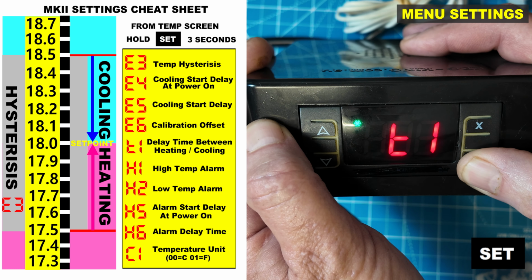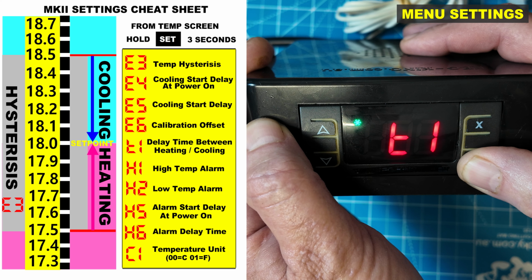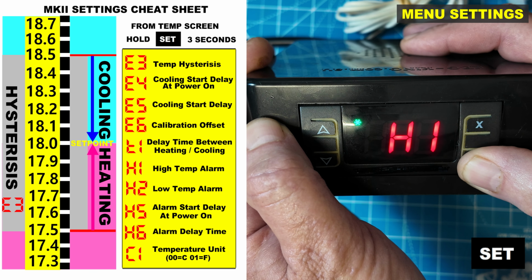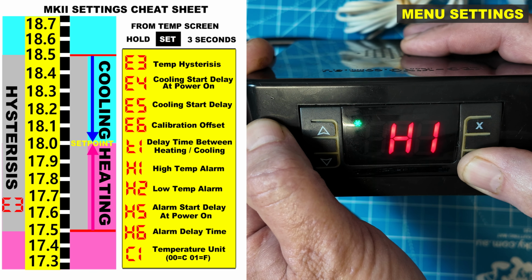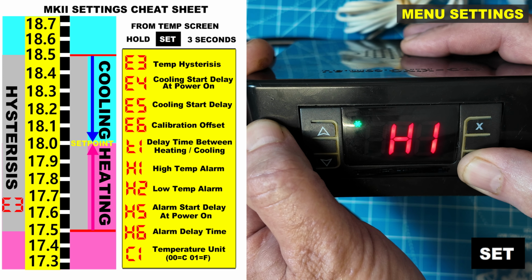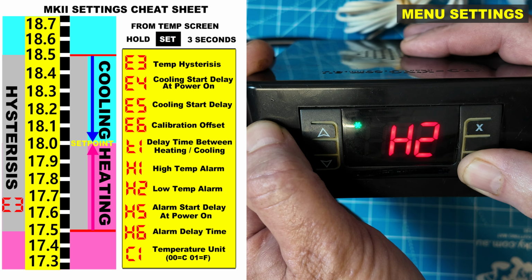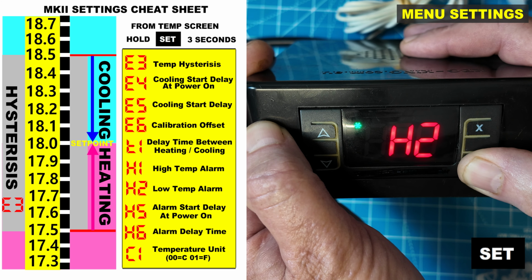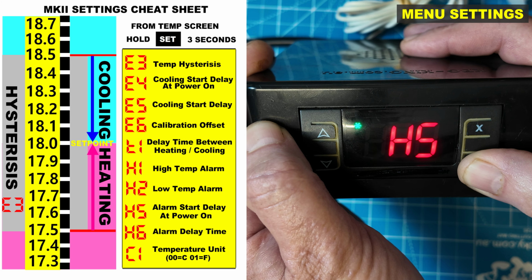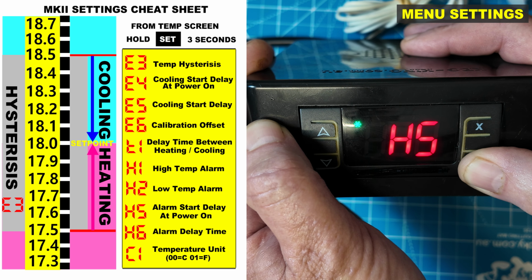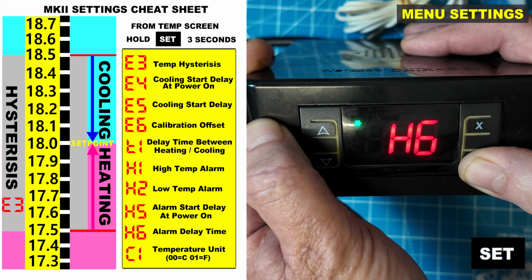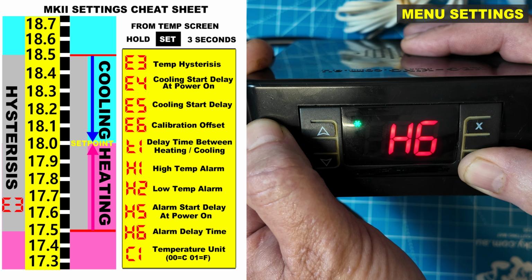I've got T1, which is the delay time between heating and cooling, and that's to prevent any overlap. H1, high temperature alarm. This sets a maximum temperature before an alarm triggers. H2 is a low temperature alarm. This sets the minimum temperature before an alarm triggers. H5, an alarm start delay on power on. This allows for a bit of a grace period before the alarms activate. H6, alarm delay time. This delays the alarm trigger when the temperature exceeds the set limits.